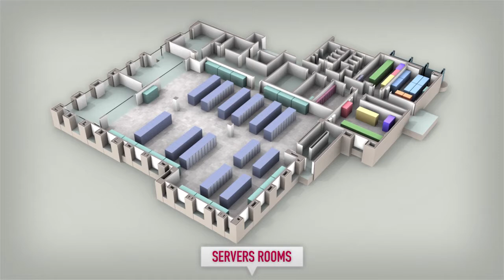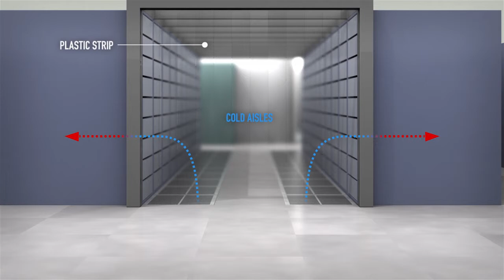Server's room. In order to reduce migration time and harm to existing equipment, the migration process will be as follows. First, plastic strip curtains will be installed surrounding the existing racks, containing the airflow in the cold aisles. Air overpressure in the cold aisles will avoid dust and particles entering the racks, thus protecting electronic devices, switches, etc.